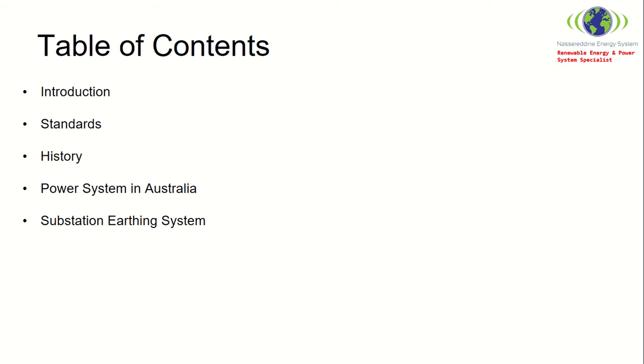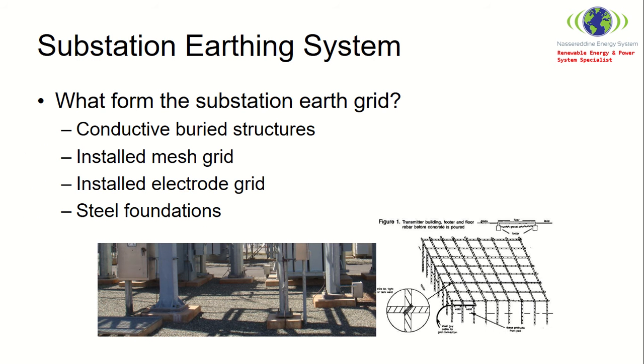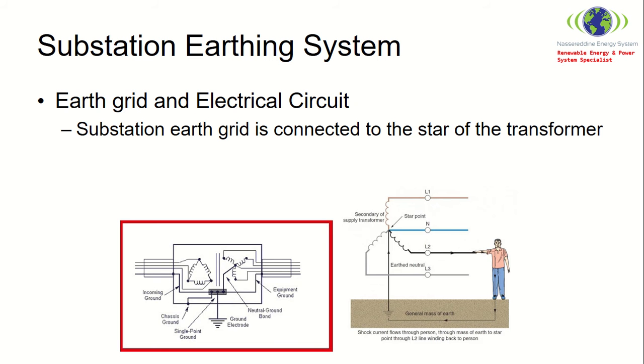The majority of this information will be built on previous experience. Before we start — what forms the substation earth grid? You'll be very surprised that every single conductive structure is made a solid part of the earth grid. The foundation of every post, all the conductive structures, must and shall be bonded together and at the end will be bonded to the earth grid.